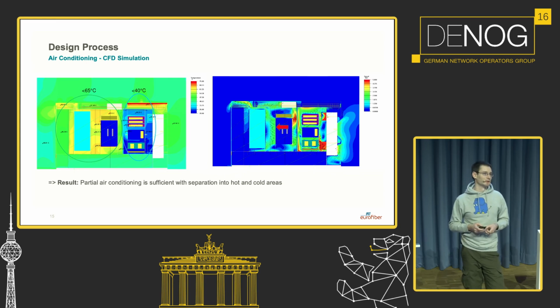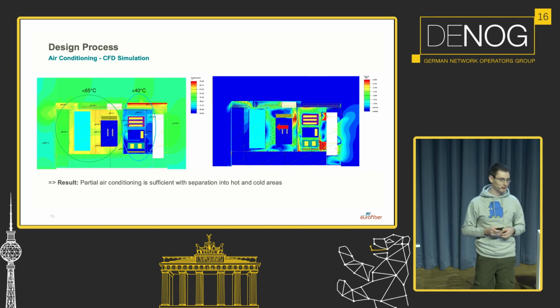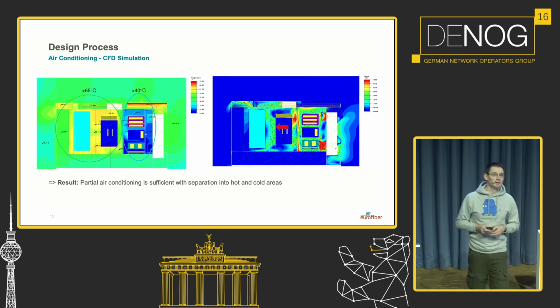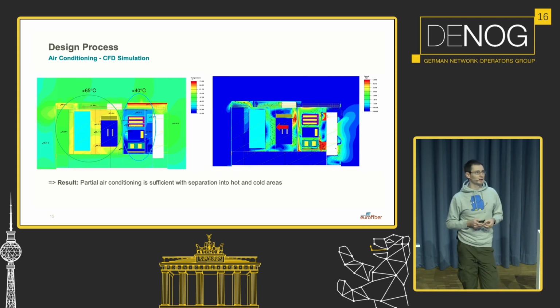They stay below 65 degrees just by passive ventilation of air, exchanging it with the outside. This heat simulation was really useful for us because it confirmed we could have smaller air conditioning units, which consume less power, by only air conditioning one of the compartments.